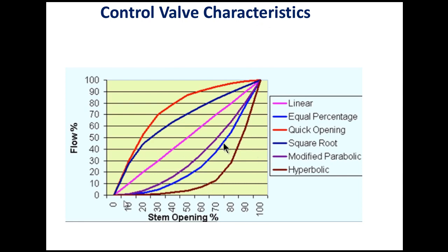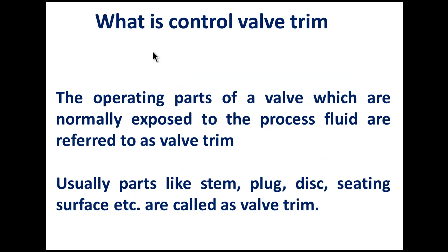Control valve is a device used to regulate the flow of liquid or gas. Control valve characteristics: three major types — quick opening, linear, and equal percentage — based on percentage of stem opening and percentage of flow. Quick opening means maximum flow is achieved with minimal stem opening. Modified characteristics include square root, modified parabolic, and hyperbolic. Control valve trim refers to the operating parts of a control valve normally exposed to the process fluid — components like stem, plug, disc, and seating surface.